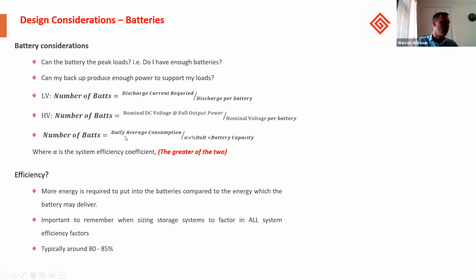battery. And then another consideration we need to understand for the number of batteries is the amount of storage required. So we look at the number of batteries as the daily average consumption divided by the efficiency factor times the depth of discharge we set the daily cycle to times the battery capacity. And the number of batteries would be the larger calculation between this and these two, depending whether you're using low voltage or high voltage. Efficiency factors in systems are typically around 80 to 85%, and that can be used as a general rule to determine the size of the system.